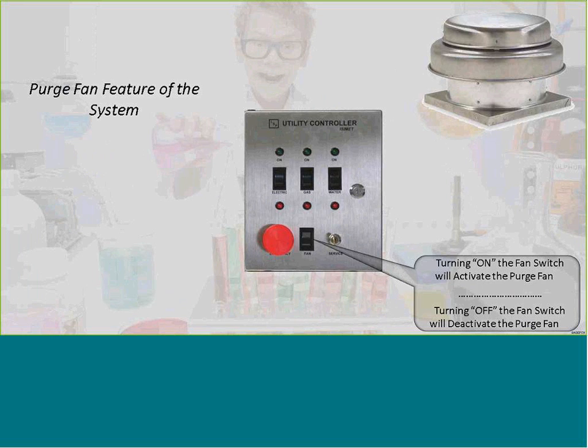Now the purge fan is used so that if you have an experiment and you're creating some odors that you don't want, or you have a slight chemical spill that has gas floating in the air and you want to exhaust that out, there's a switch on the control panel that can be turned on and off without activating the key. That's the key thing. The fan needs to come on when they need it. Also, the fan will come on when you hit the panic button.